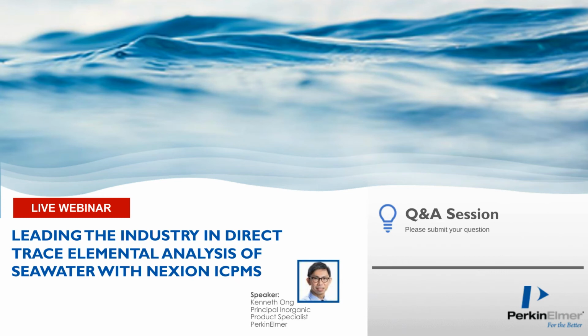Hi, that's a very broad but a very good question. The thing about seawater, as we have discussed, is that it contains high dissolved solids. So you need an ICP-MS that has the robustness to handle the matrices. The second thing is that a lot of ICP-MS are very concerned with drifting.